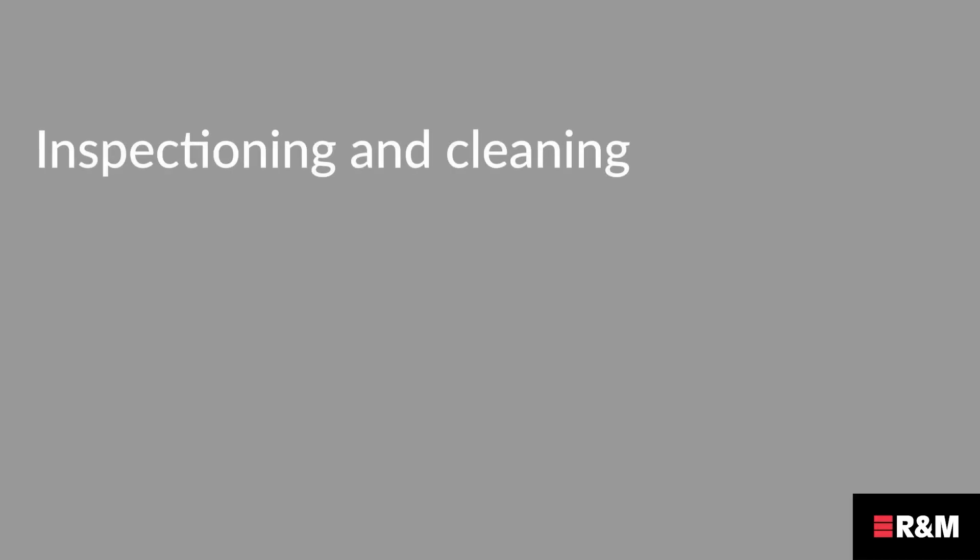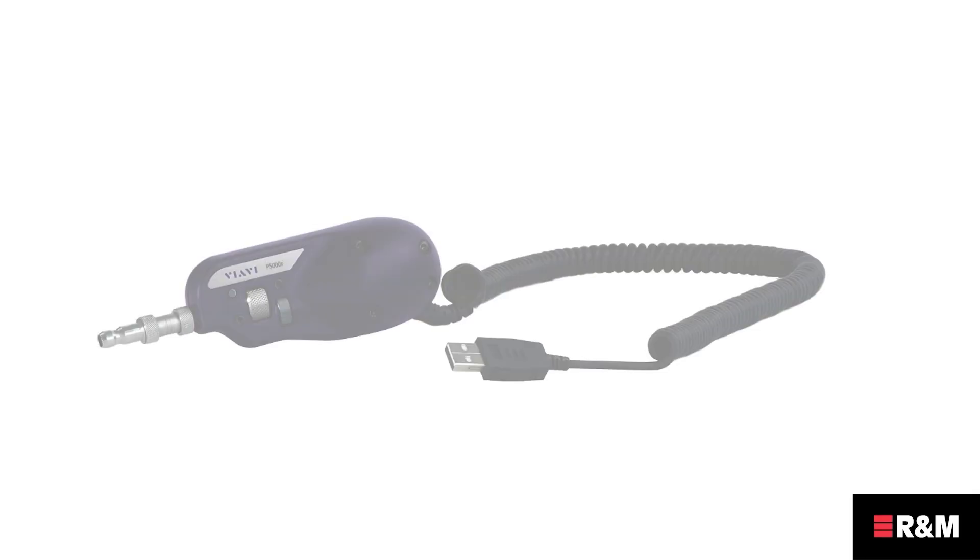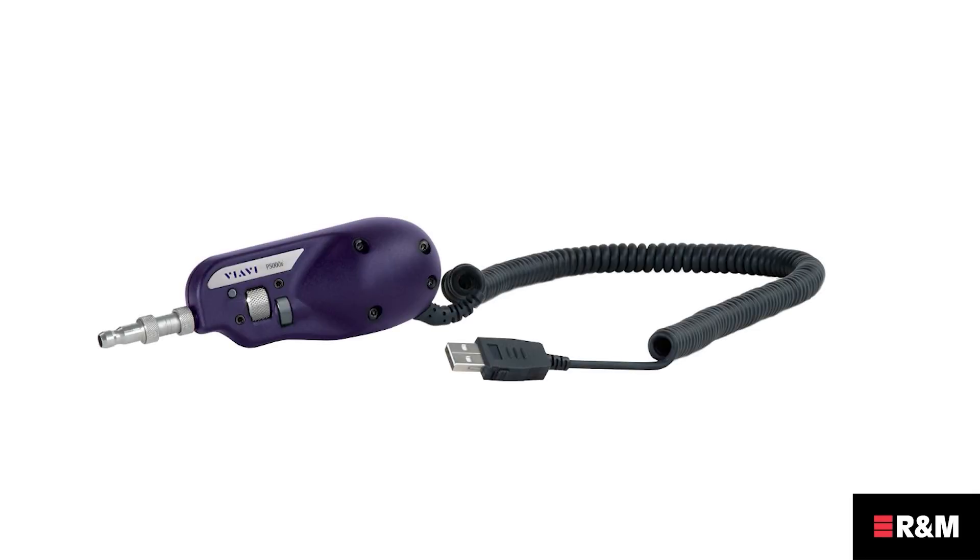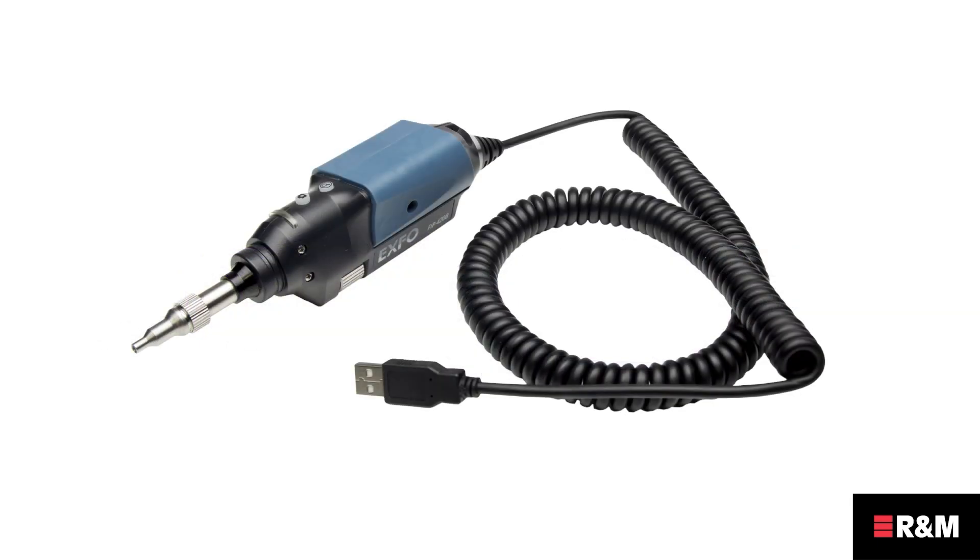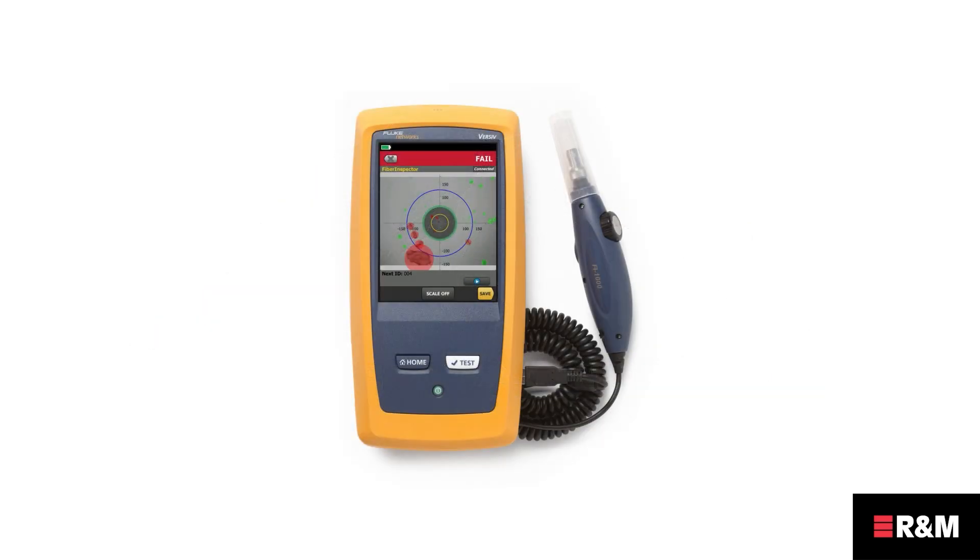Inspection and cleaning is an essential part to all testing procedures. Firstly, the condition and quality of the reference cords must be verified by inspection. In order to check the connector quality of the test reference cords, a microscope must be used. There are different kinds of microscopes on the market. We at R&M strongly recommend the use of video probes. These are 100% safe and can even be used to check the connector quality of active fibers.